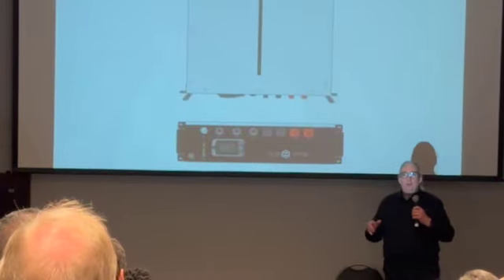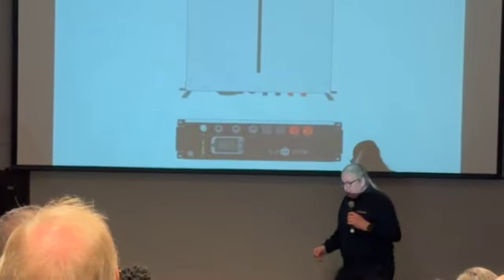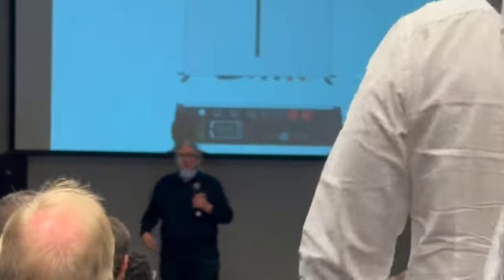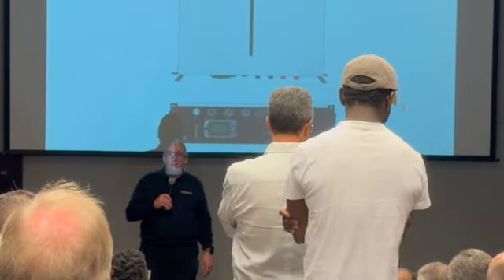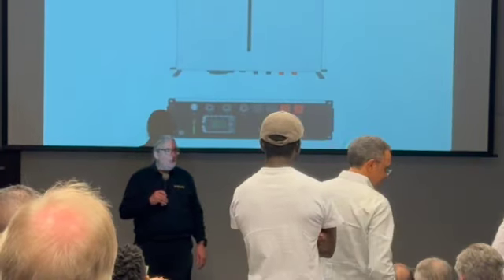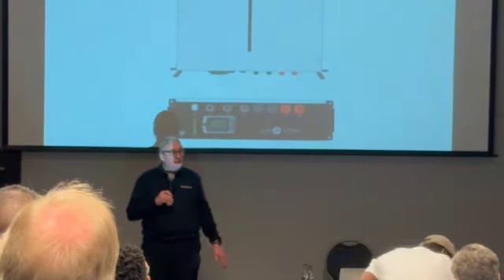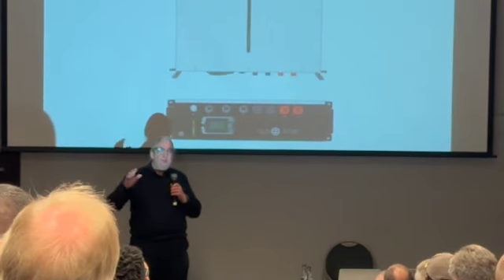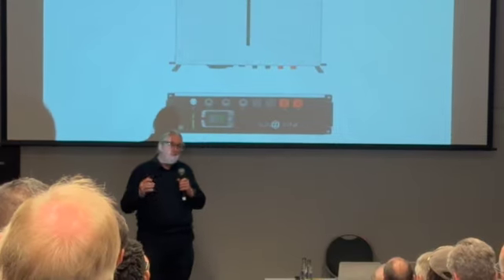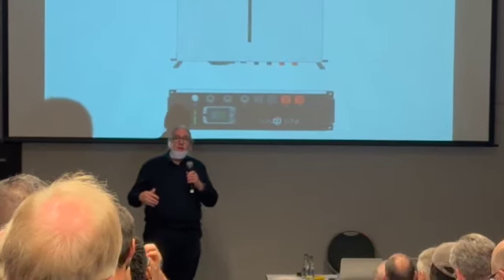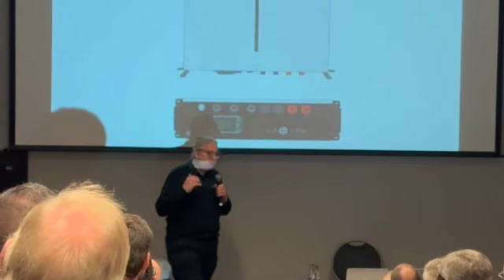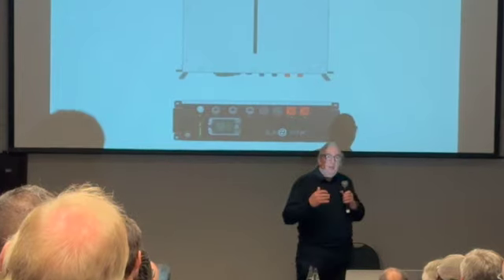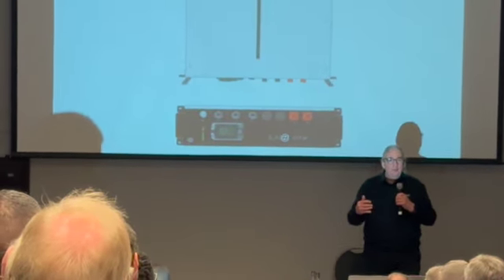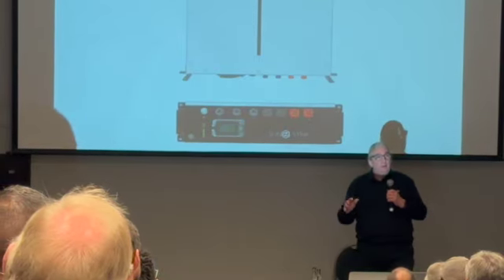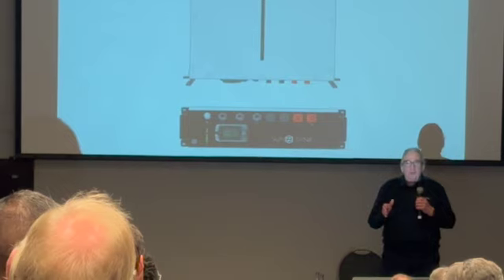The reason, as you've probably heard people talking about, comes down to earth bonding and earth bond relays. You might say we don't need earth bond relays, and in some cases you probably don't, you can put a permanent bond between neutral and earth. But certainly in the UK you can't, and in many applications here you can't either, especially with upstream RCDs, because a permanent bond will trip an upstream RCD feeding the inverter. You have to have the earth bond go downstream, because its purpose is to change the classification of the inverter from class 2 to class 1. If you don't change it to class 1, it becomes dangerous, there's a risk of electrocution, and none of your RCDs will give you any protection. That's the main reason you have it, it's to do with the classification of the inverter.